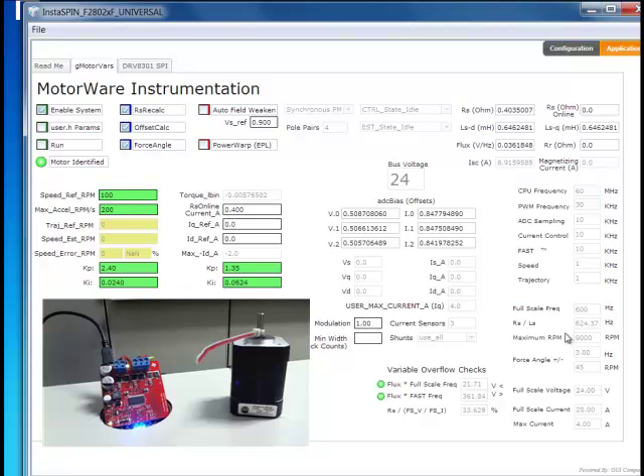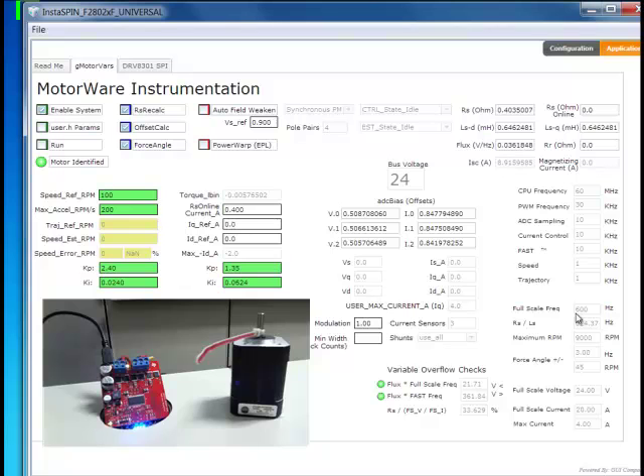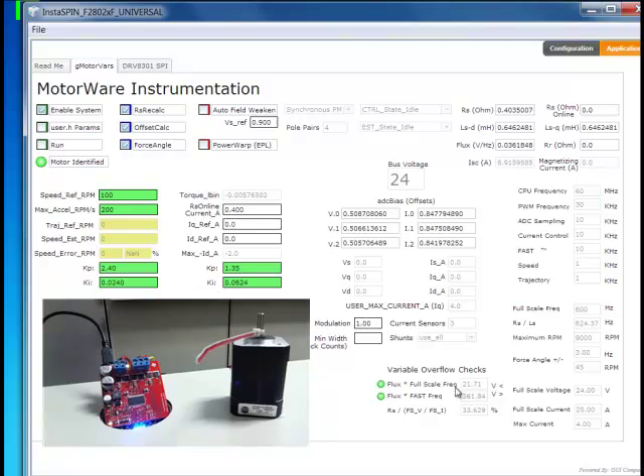I've also done some other checks here. I've taken resistance divided by inductance, and that gives you a good idea of the maximum theoretical speed of the motor. And I've used that to actually update my full-scale frequency to a value that makes sense. Also, during the identification, as the values for flux became accurate, this gives me a good variable check that I explained in the Quick Start Guide to make sure that I choose the best selection for my full-scale voltage that makes sense for my system.